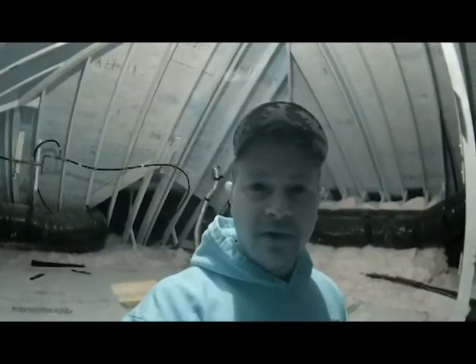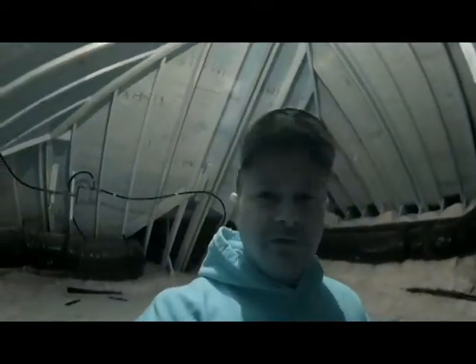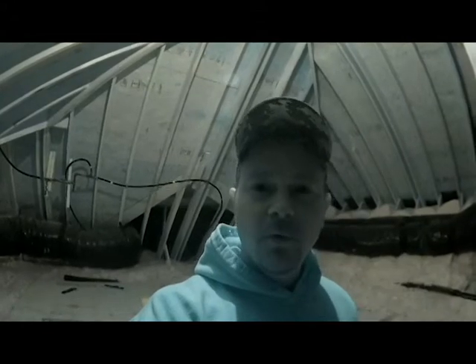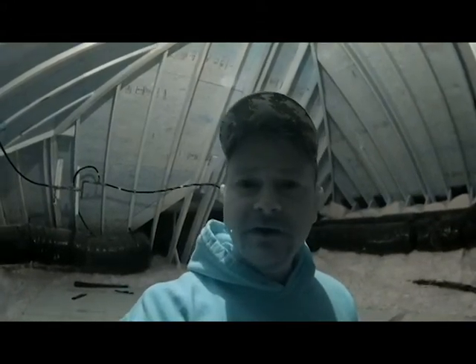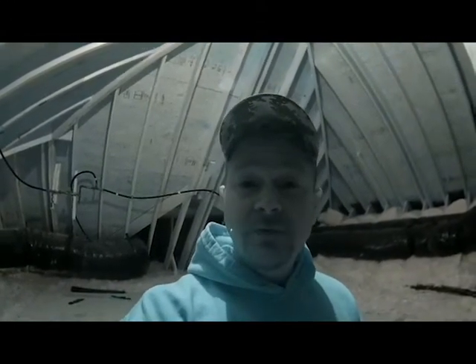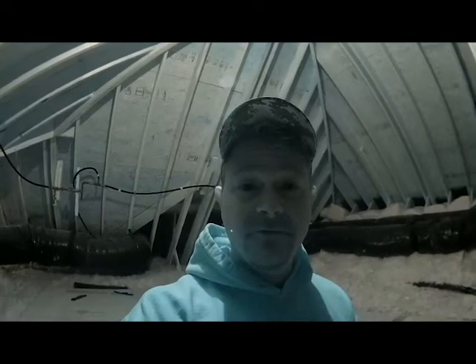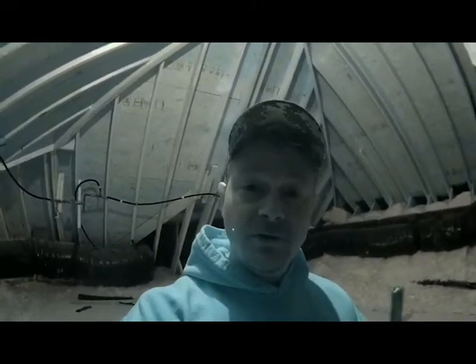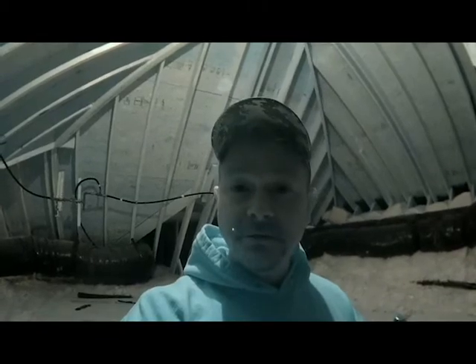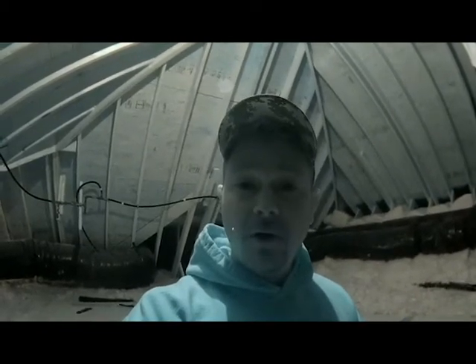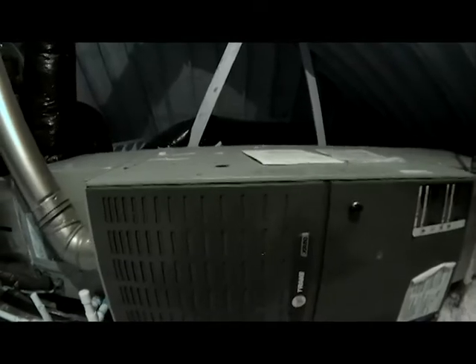Okay, guys, we're up here in the attic at the furnace. Now, the first thing we want to do when we're trying to determine the correct temperature rise of a furnace is find the nameplate of the furnace itself, because the range of your temperature rise should be on the nameplate. Our nameplate on this one is located inside the furnace, so we need to take these doors off and find that nameplate.